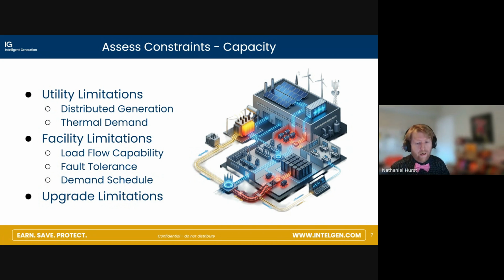Okay, assess constraints and capacity. This is a big one, and a very different situation with batteries compared to solar. This graphic is a bit eclectic, but it gets the point across. With solar, we benefit from the fact that it only generates, so your utility can both push or pull, your solar can generate, and your site demand can only pull. In that three-way junction, your solar is always either draining into your customer or into the grid. Because of that, all three legs of that junction could be the same size.